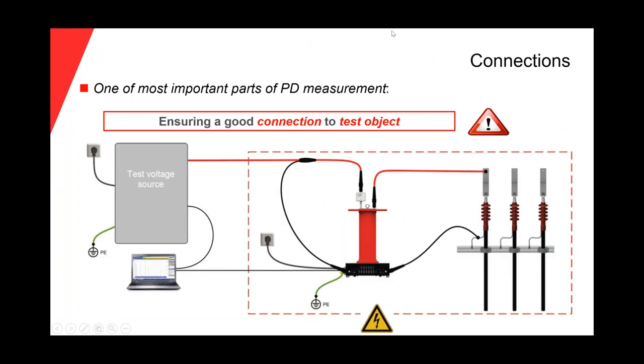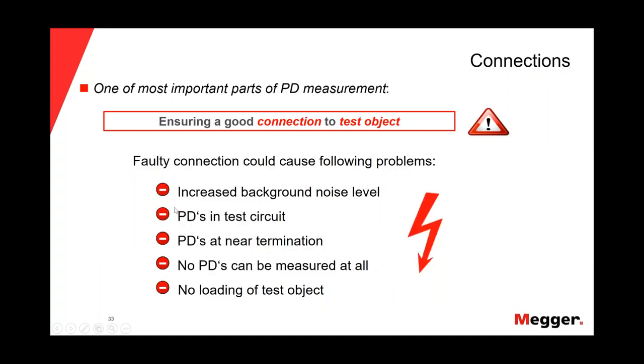So what is important when we are doing a PD measurement? One of the most important parts of the PD measurement is ensuring a good connection to the test object, okay? You are seeing one example of the connection of the setup, the connection of PLF with the coupling capacitor, okay?